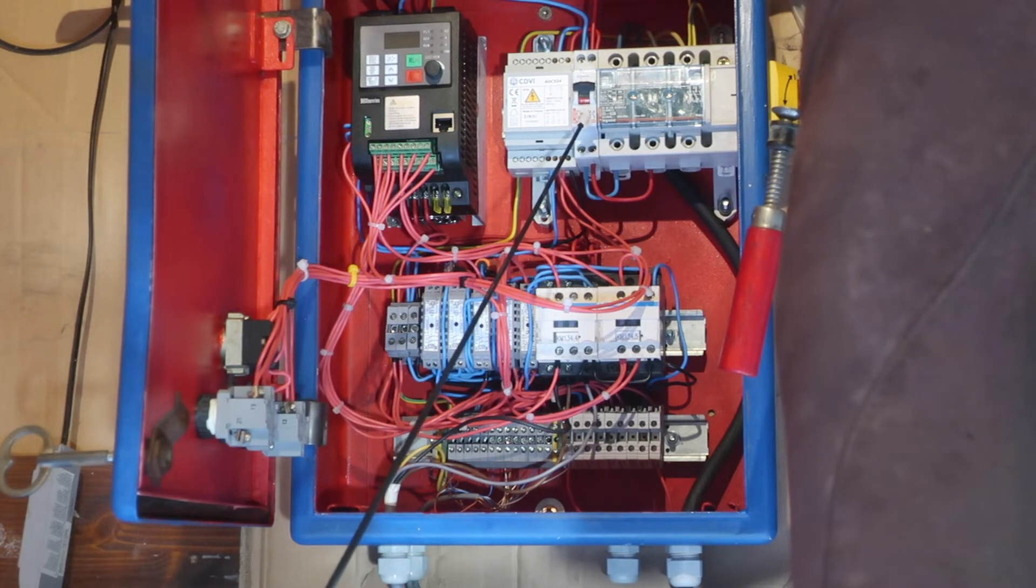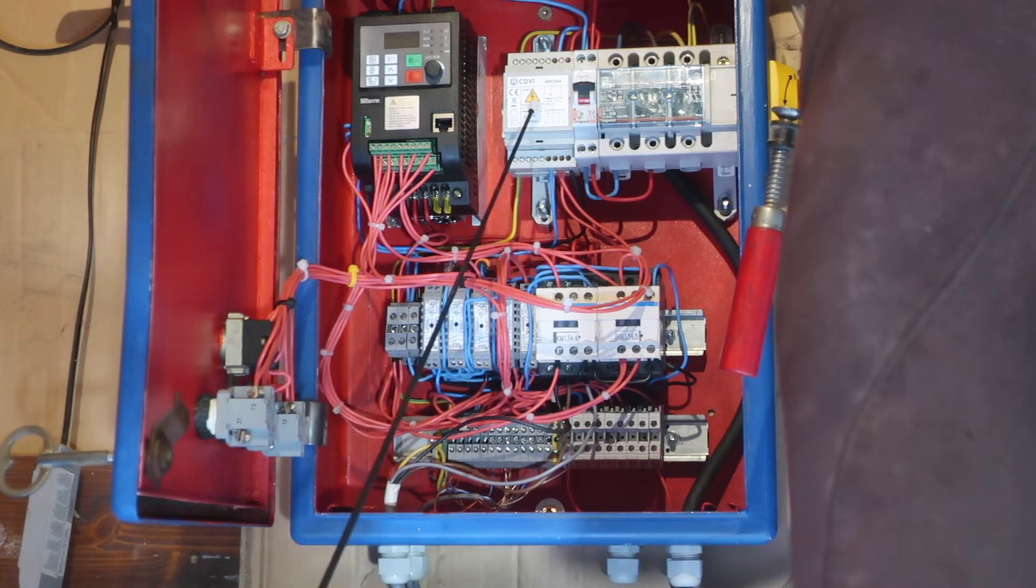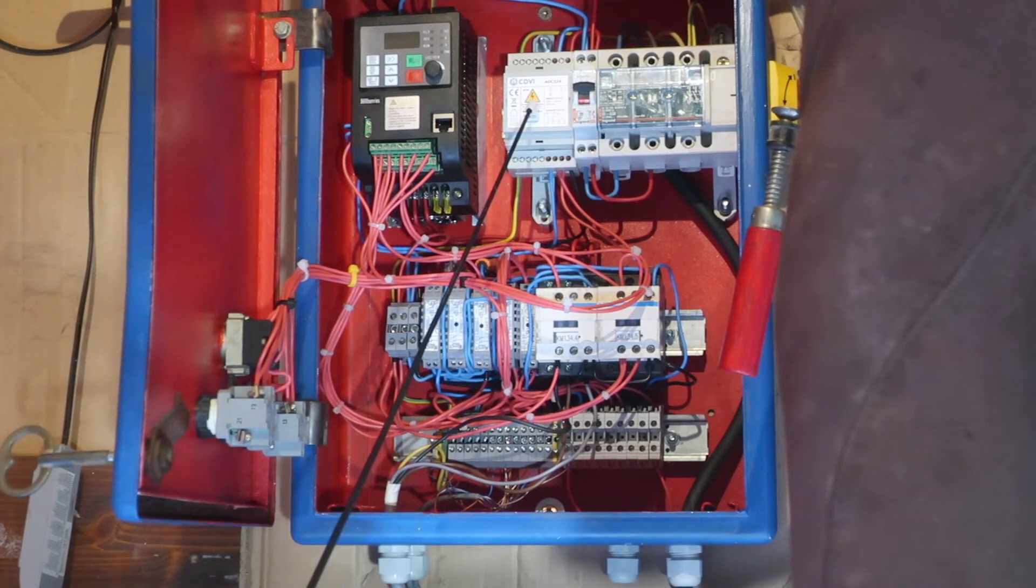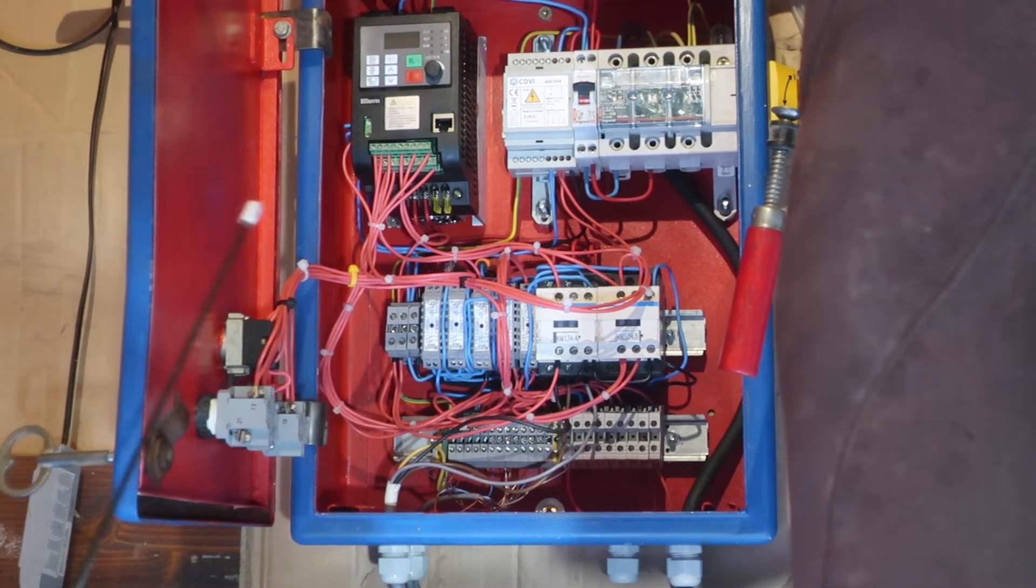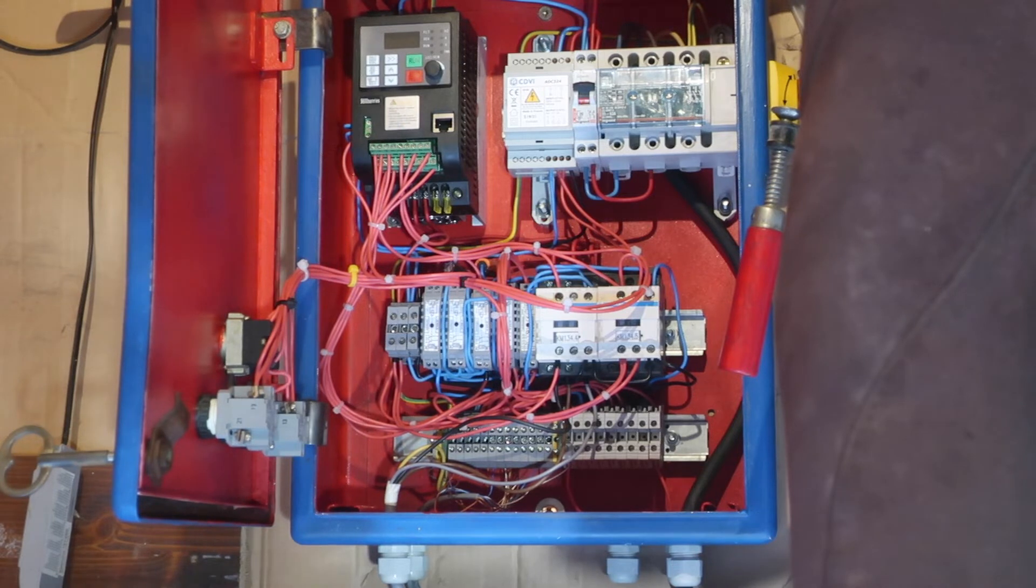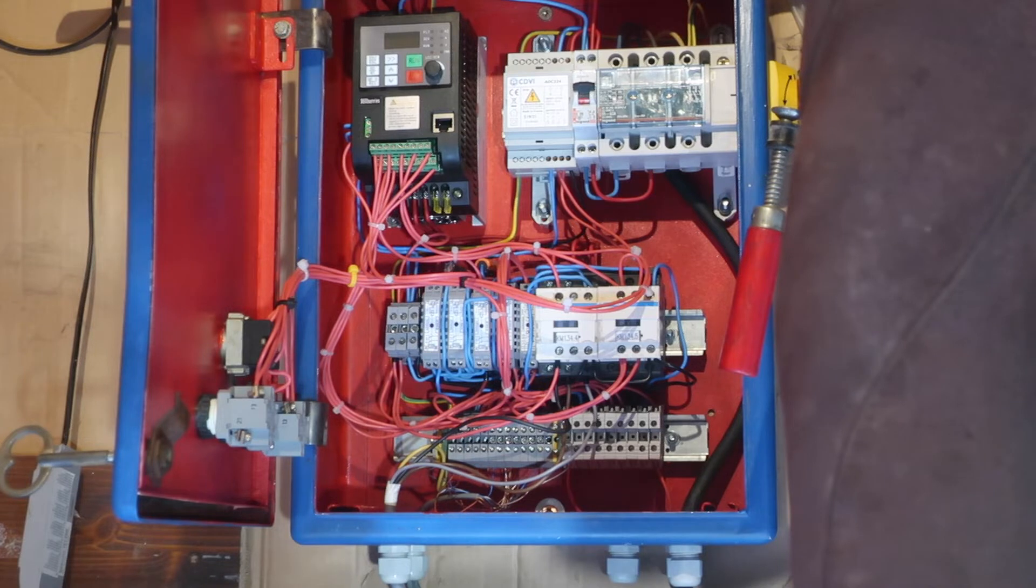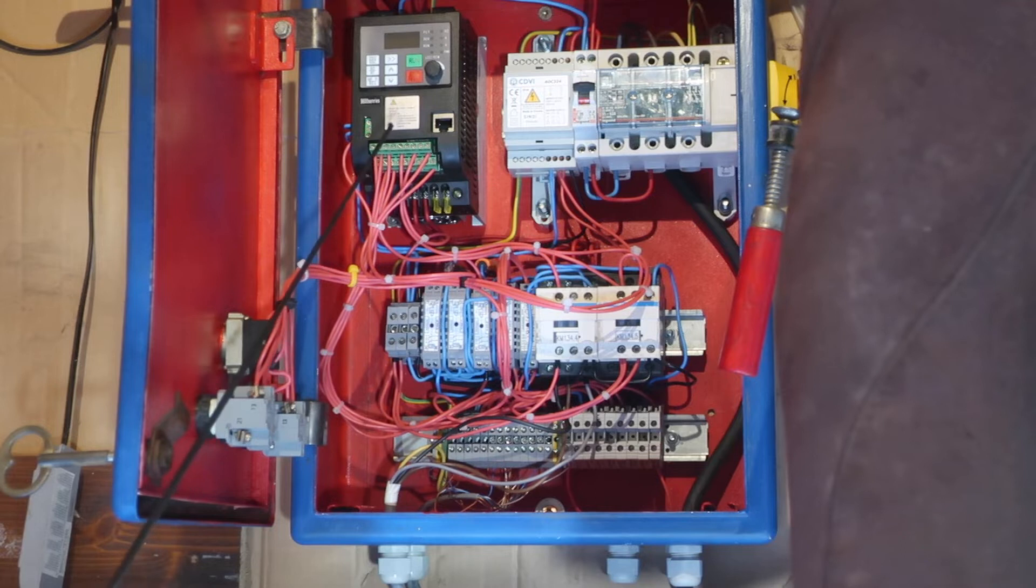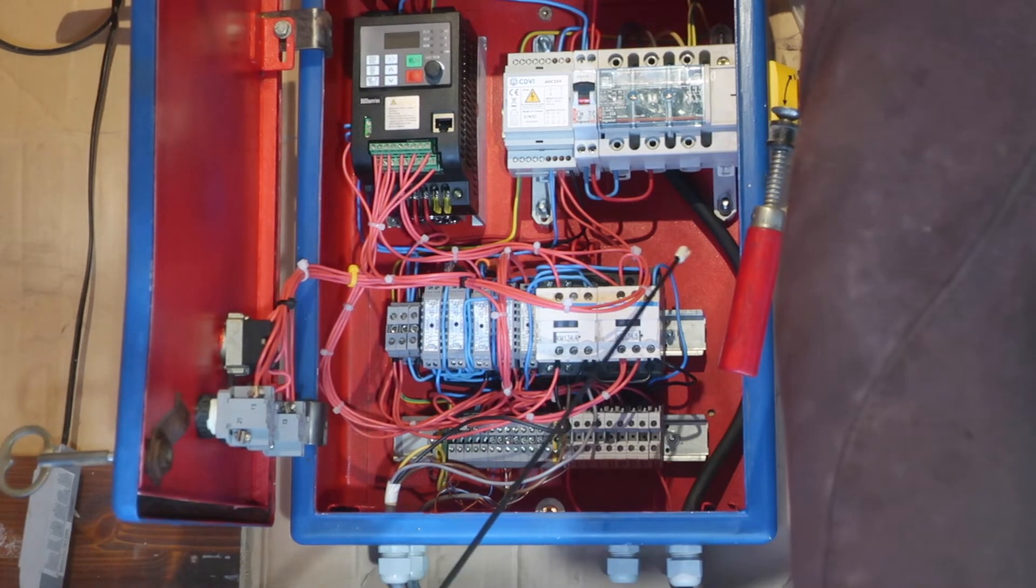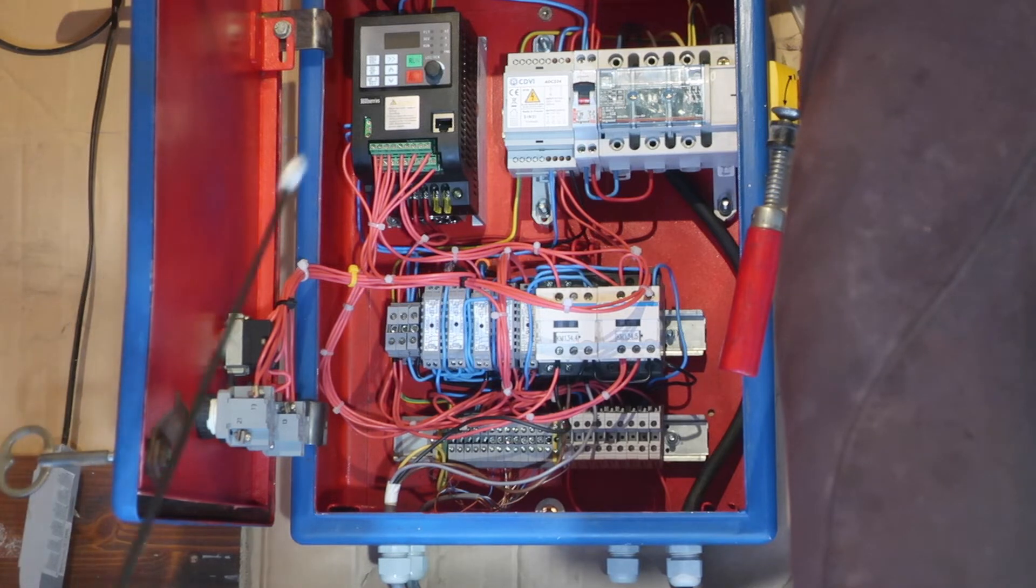Here we have a 24 volt supply which runs off 220 volts. There is a slight problem with these variators in that you can't use an external 24 volt system to drive the 24 volt signaling. You have to use the internal 24 volt signaling, but it doesn't have enough beef to drive contactors. So it's a bit of a problem.